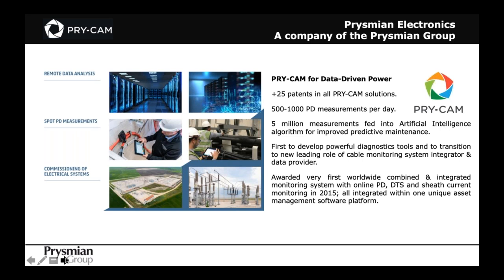Our hardware and software solutions include more than 25 patents with an original focus on partial discharge measurements. This won't be the main theme of this presentation, but it's important to point out that one of the main reasons medium voltage and high voltage electrical assets fail is related to partial discharge. As a company, we take approximately 500 to 1,000 PD measurements per day, and now have an incredible library of more than 5 million data points. Those measurements are fed into an algorithm which helps us improve prediction on electrical assets when monitoring those systems.